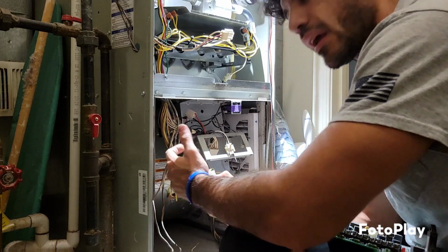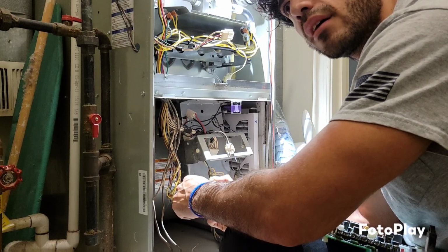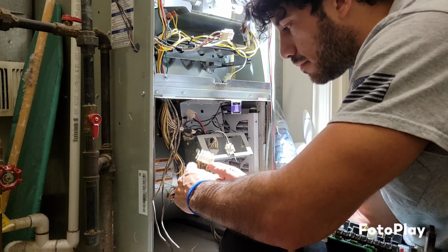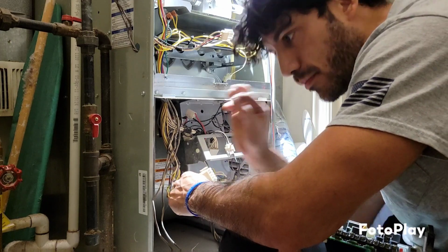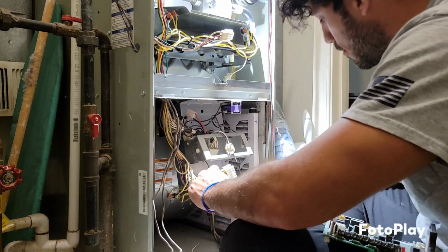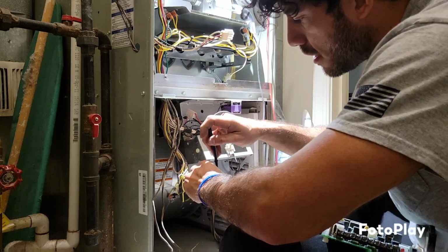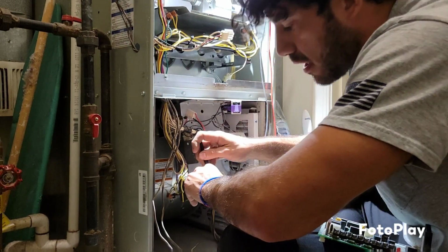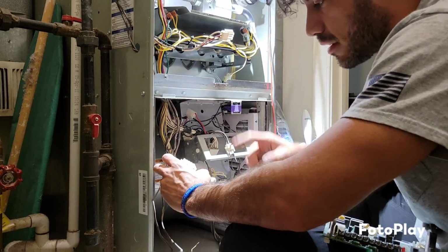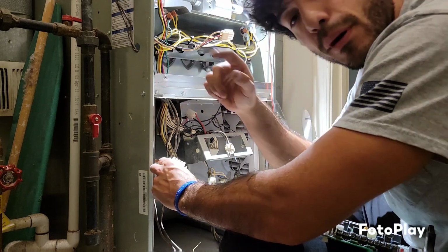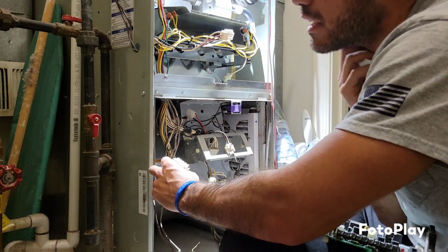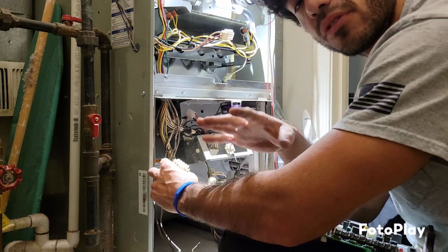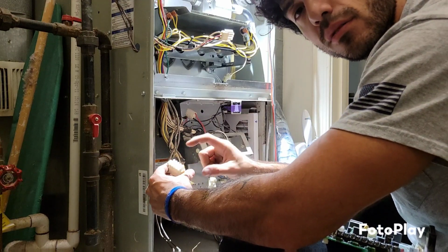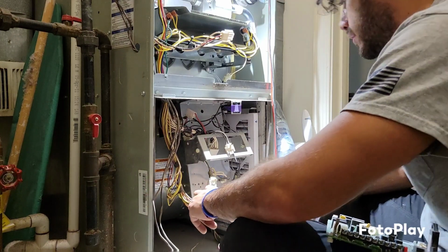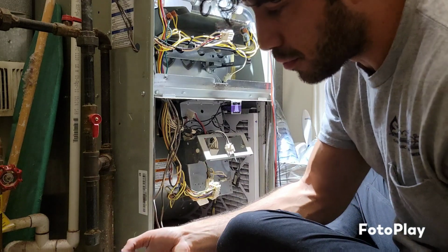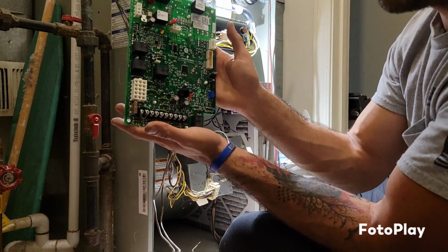A lot of times you'll notice that if you jiggle it, or put your meter probe in there and crimp them all up, then turn the power back on, and the unit will run. So you'll notice you're losing something somewhere, and it might be because of these harnesses. Just double check that all the time. But we're gonna mount the new board right now, which is this guy right here.